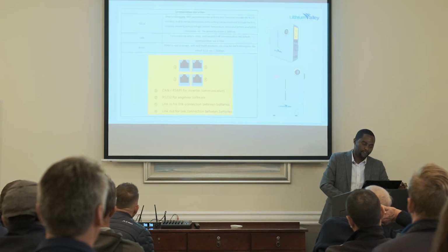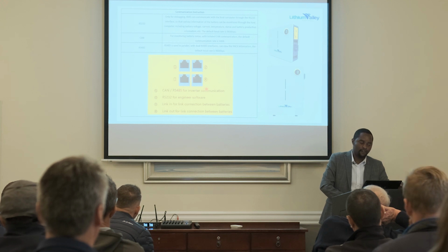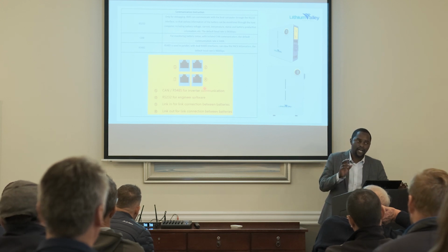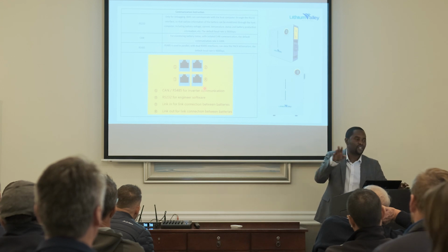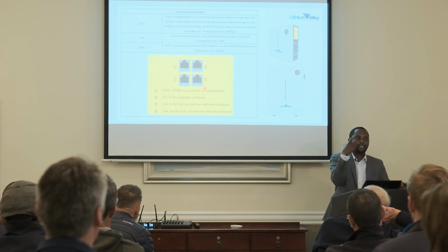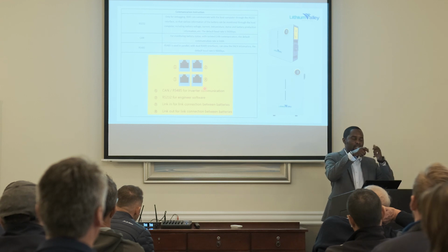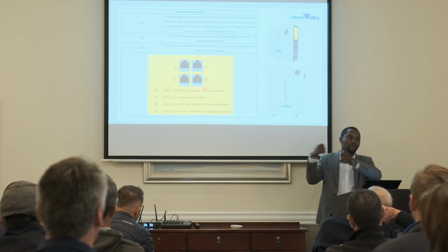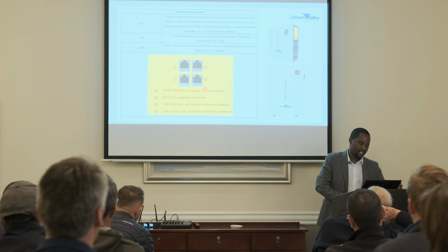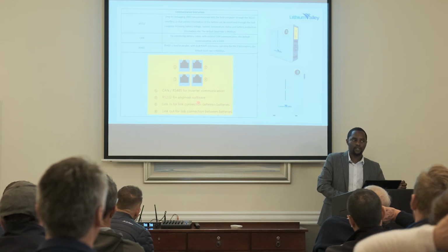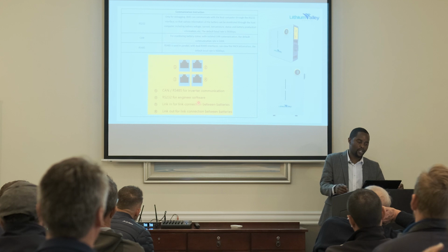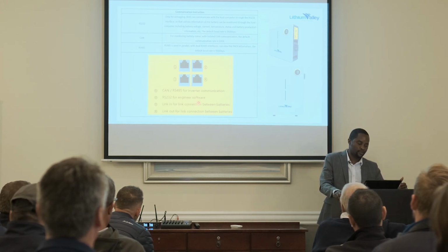Then you've got different ports here. We've got the link A and link B, in and out. That is your 3 and 4 here. Then these ones, whereas the other batteries now you need to put in, out, in, out. These ones you can put them anyhow. It's the same daisy chain. So it doesn't matter when you're going to invert out your battery, you can put it on any port. You don't need to be extra careful, right? Then the CAN and the RS-485 is provided for your BMS. Then you've got also an RS-232 port that you can use for programming when you want to program or you want to calibrate, do the manual calibration of your system.